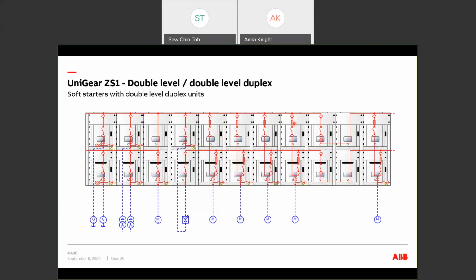So how do we use this type of duplex cubicles? Here's an example. The switchboard has 2 transformers coming in and also 2 generators coming in. In this section of the board, as you can see, these are actually the double feeders, 2 feeders feeding into 2 loads. And what duplex is doing is to the right hand side of the board. The duplex design is normally used in a multi-motor starter, meaning we use one VSD to start multiple motors.